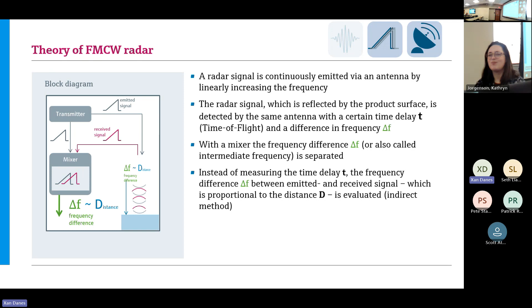When we say what's new with new radars, they're very efficient. The measurement itself no longer needs that pulse generator. If you look at that chip on the right, and then the electronics specifically, we would traditionally need the transmitter electronics - that's where the signal impulse gets generated. That's typically connected via a high frequency cable into the back of the sensor electronics in the antenna. So we'd end up with a 3-part measuring system, and those three parts are all very sensitive to anything that could change.